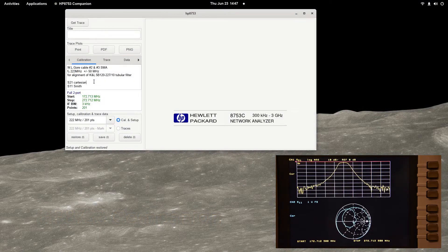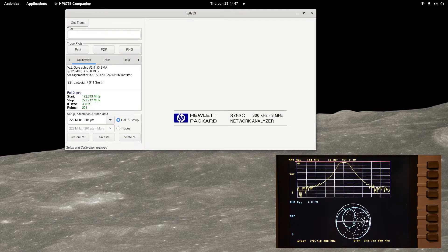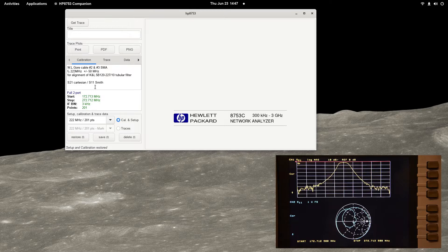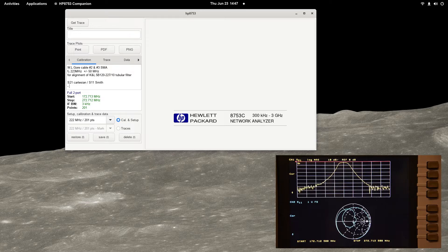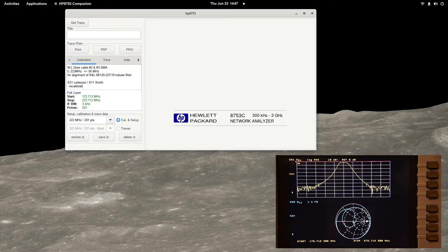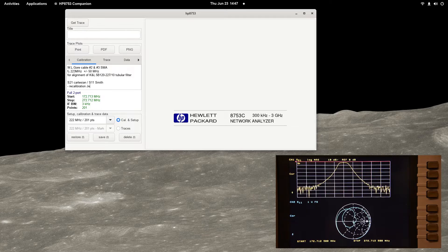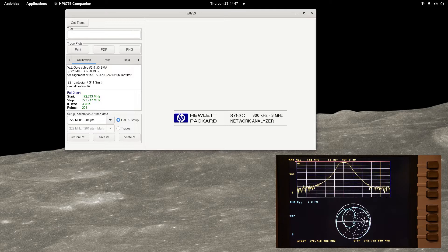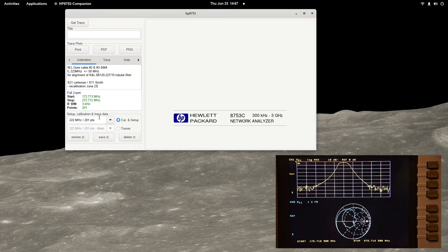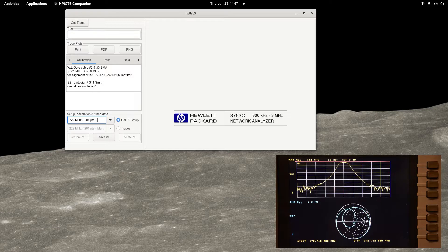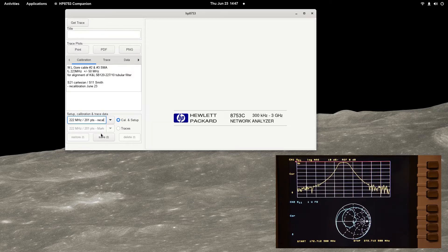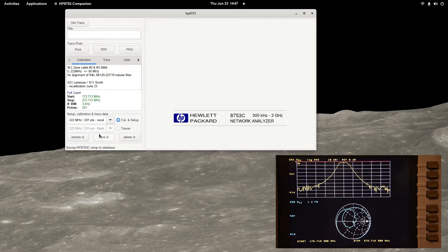A note can be written to accompany the setup and calibration profile. This can aid in identifying the setup prior to restoration. To save the setup, type a name in the calibration edit box or select an existing profile to overwrite. When the save button is pressed, the LearnString and calibration error correction vectors are extracted from the analyzer and saved to a database.